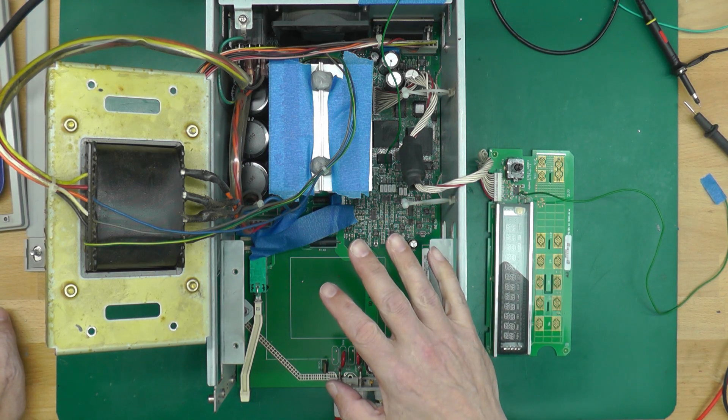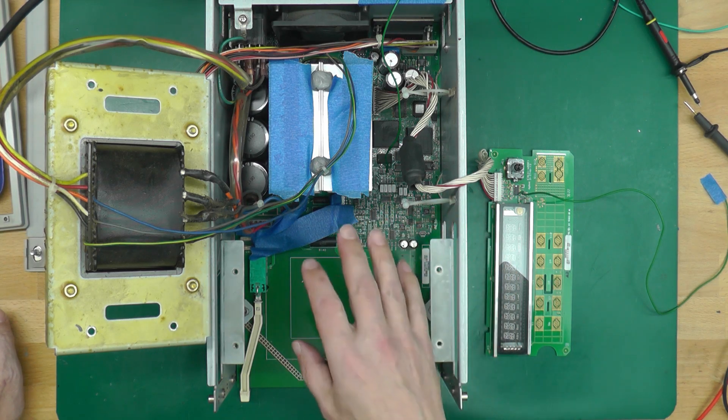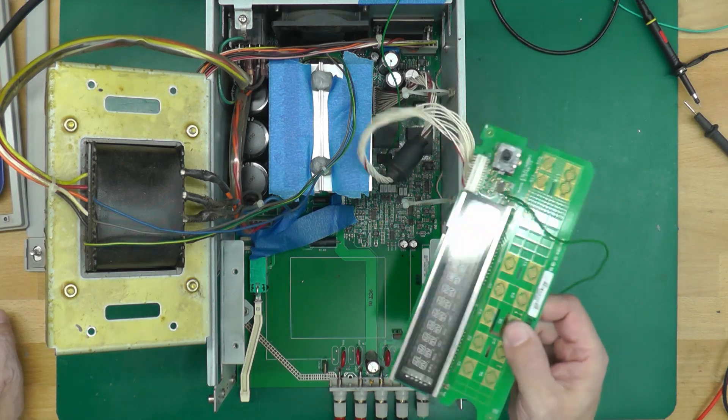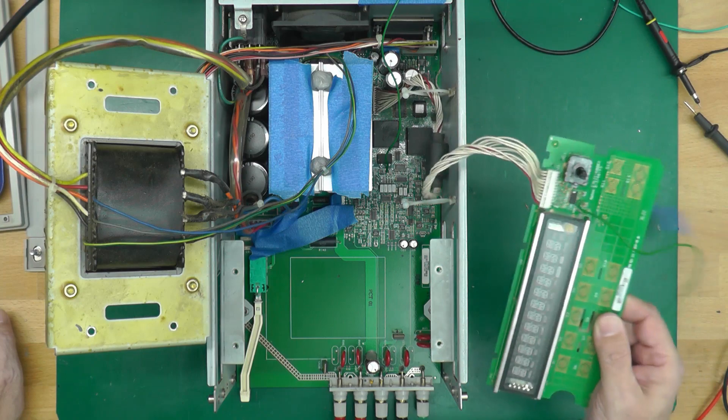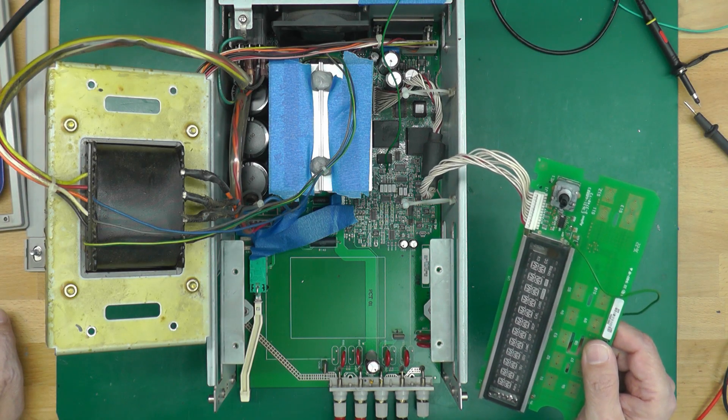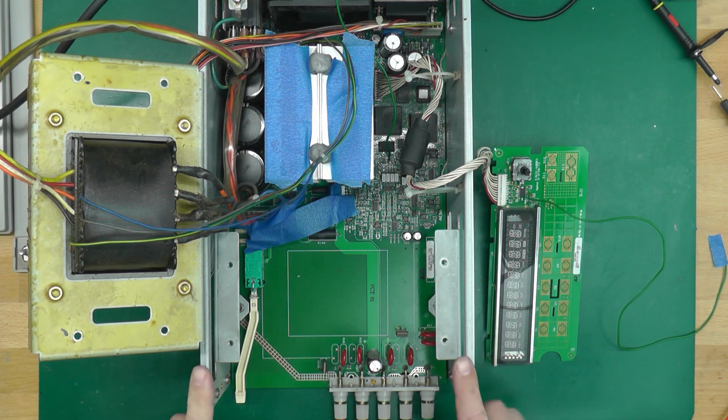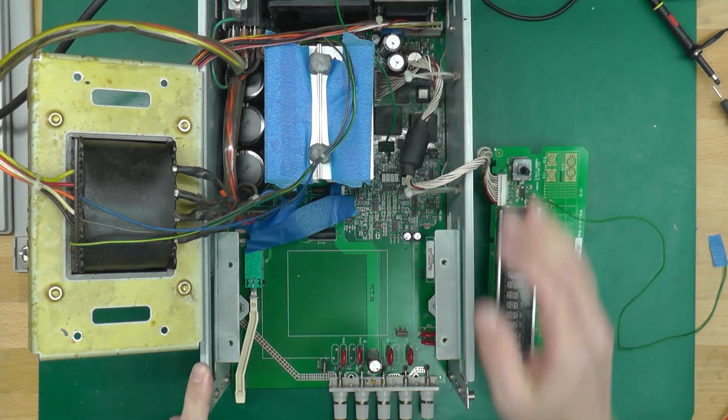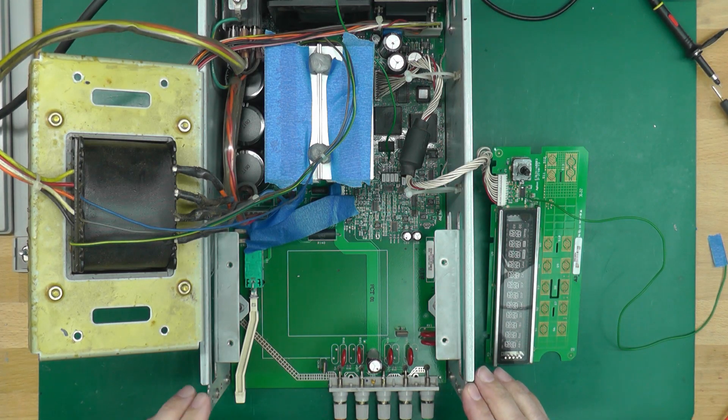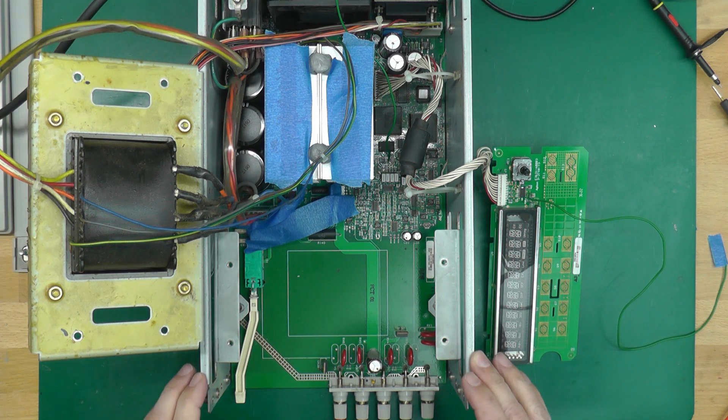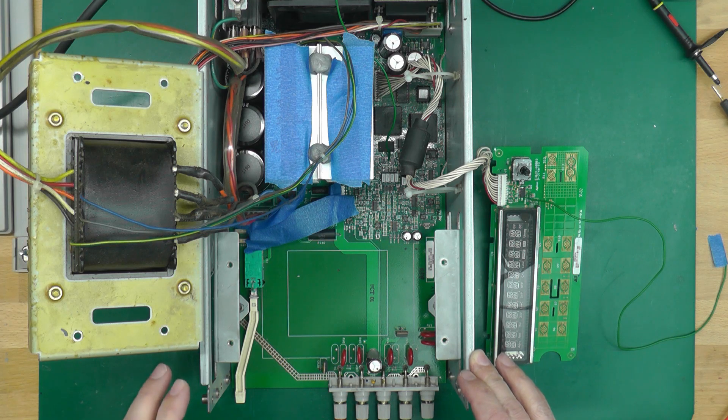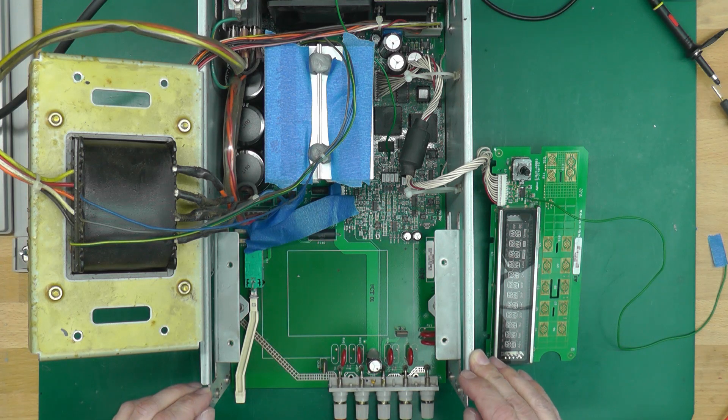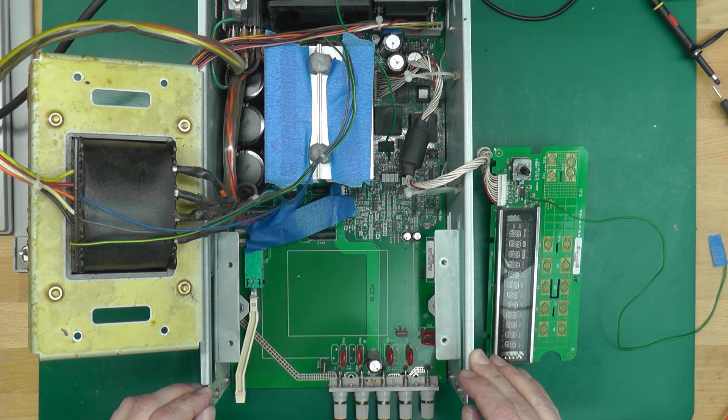But I'm definitely not getting any serial data either on power up between the front panel and the main board. So it's unknown at the moment whether the problems on the main board or whether that is actually a problem on the display board which is halting that serial communication. I don't really know at this moment in time. Well I just tried to connect via GPIB on the back of the instrument, but it wasn't having it. It's something there, but I couldn't connect and establish a good connection. So what I think I'm going to do is take the main board out and see if we can nail down the problem that way.